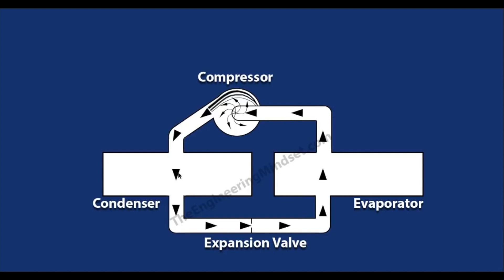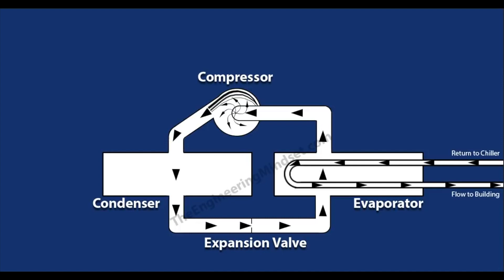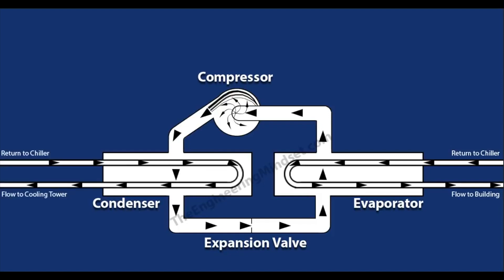There are three main circuits in a chiller you also need to know about. First is the refrigeration loop — the refrigerant which passes around each of the four components, transferring heat from the evaporator over to the condenser. The second circuit is the chilled water loop — the heat from the building being collected and sent to the chiller, then back to the building. The third and final circuit is the condenser circuit — the heat being sent to the cooling towers and returning to pick up more heat.